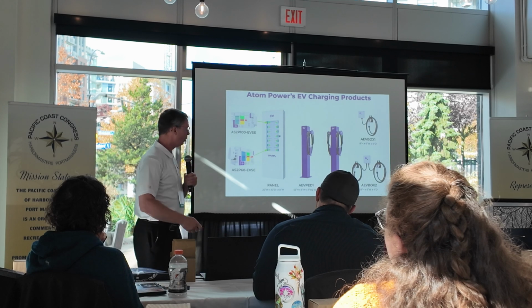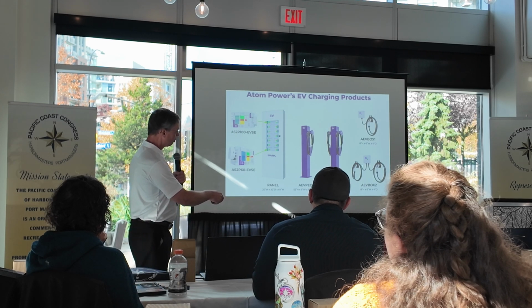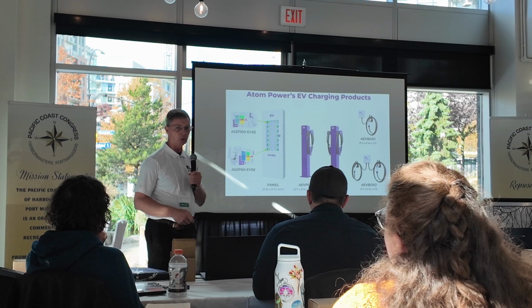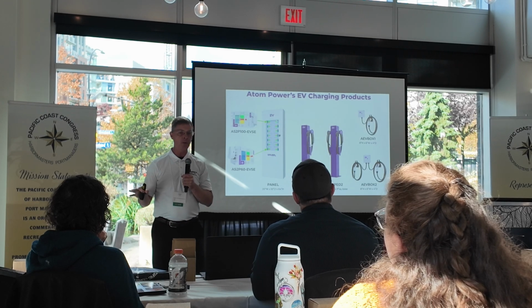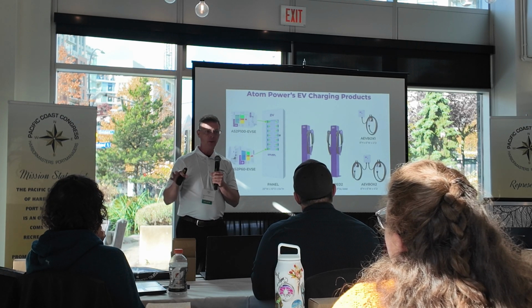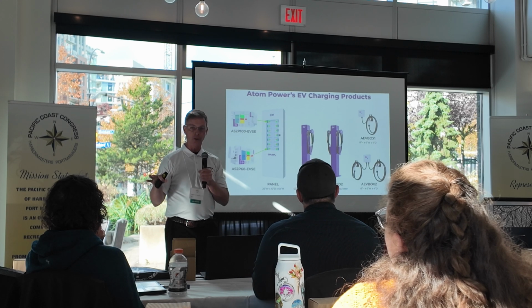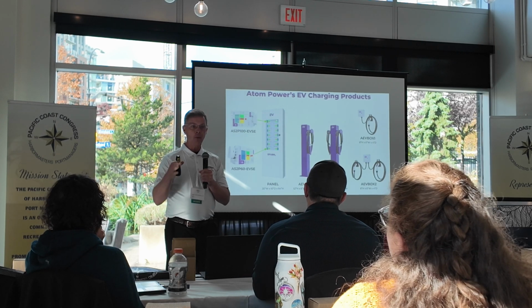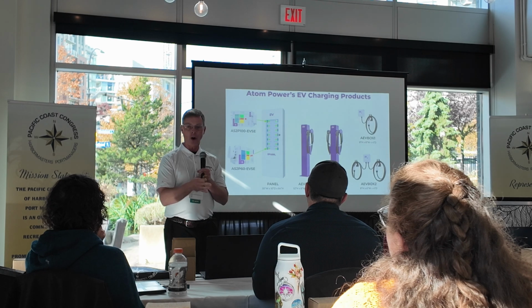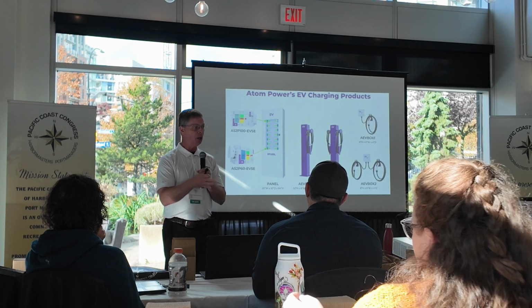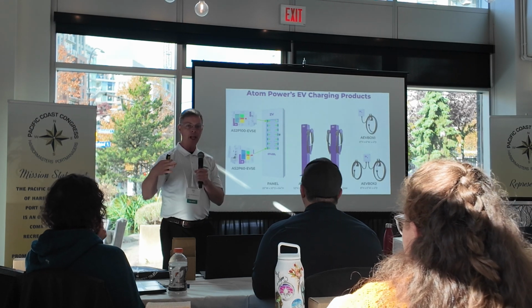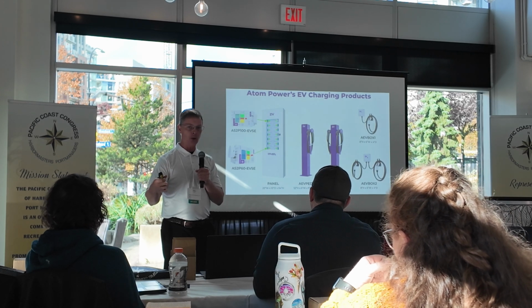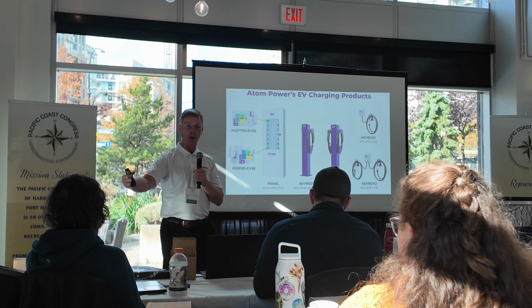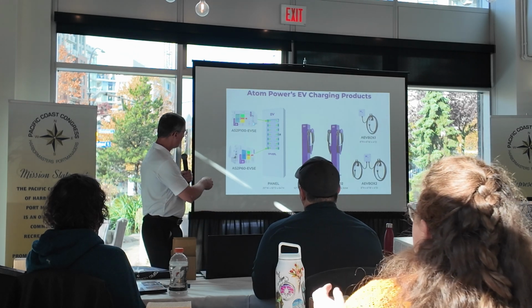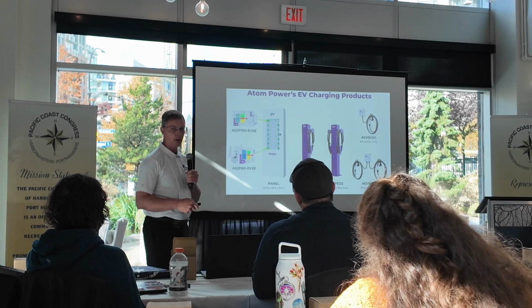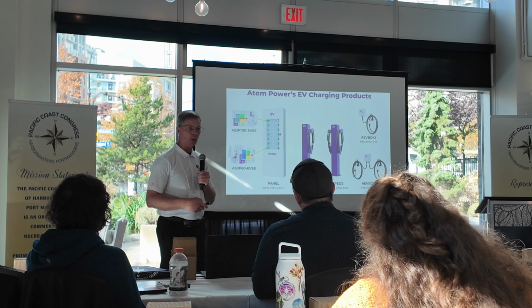Actually, you can even do that, but you can have these dual units. That could be 100 amps. So you could actually have 24 boats connected to this and charge 24 boats at one time, but the 400 amps would get distributed over the 24 boats. But then when several boats get charged and they go offline, then that extra capacity goes to the boats that are online. All the way down to the last 4 boats, and if you got the last 4 boats, you could literally put 100 amps into each boat. Because these are solid state breakers, and they do the load control, power control through those breakers, and they're smart.